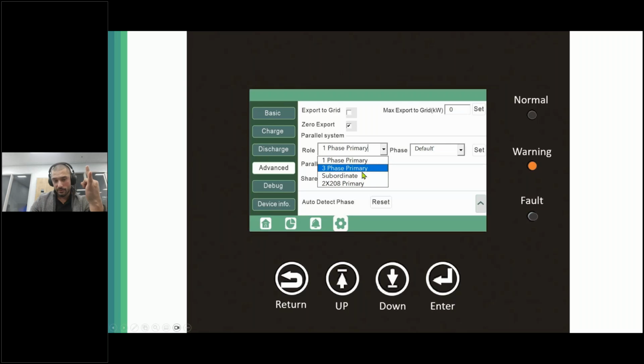If I have two inverters in a three phase configuration, which we can do, you are going to select 208 primary, and then I'm going to select for the master the R phase. But if you are grid tied, you can select auto detect phase once the grid is on, and it will assign it automatically.